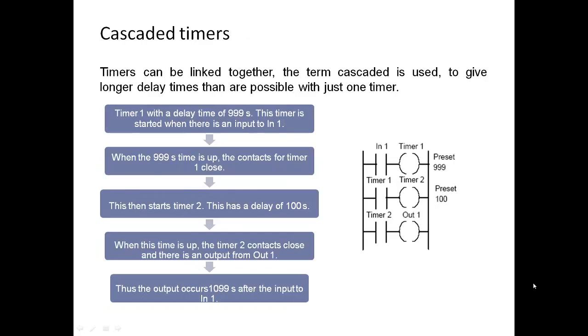Cascaded timers. Timers can be linked together. The term cascaded is used to give longer delay timers than are possible with just one timer. Timer 1 with delay time of 999 seconds. The timer is started when there is an input of IN1. When 999 seconds time is up, the contacts of timer 1 close. Then timer 2 starts with delay of 100 seconds. When the time is up, timer 2 contact closes and output from OUT1. Thus the output occurs 1099 seconds after completion of input 1.